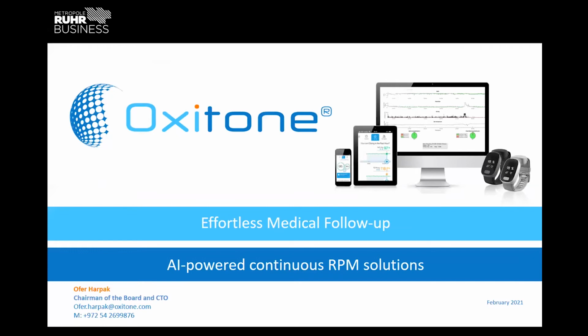Once you are a physician, you will get an automatic alarm when something goes wrong with your patient. Then you can click and see your dashboard, and you can see a list of all your patients. The ones that are in a severe situation will pop up to the top of the list and will be in a different color. If you double click on one of them, you can see a graphical presentation of all the parameters that we are measuring, starting from saturation, pulse rate, output variation, and all the rest.